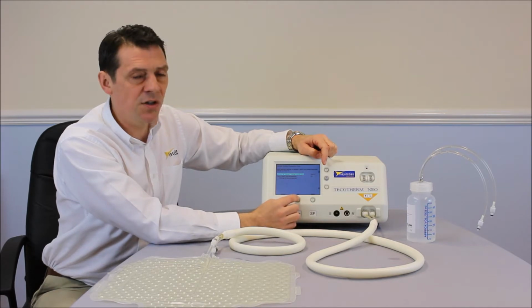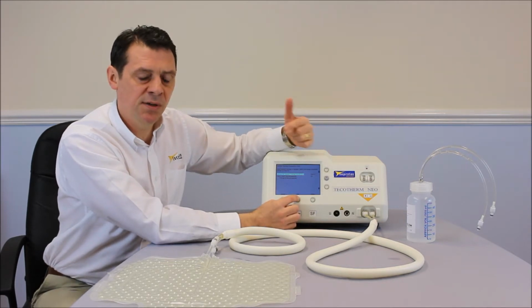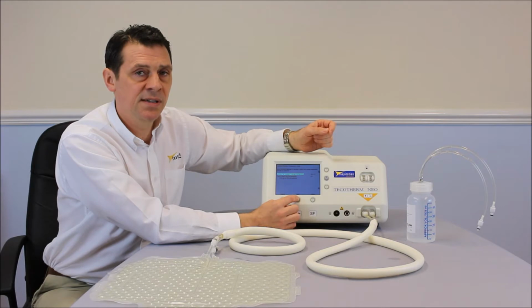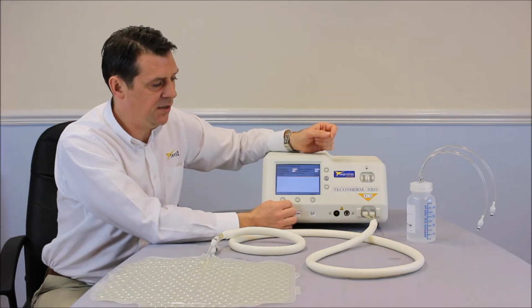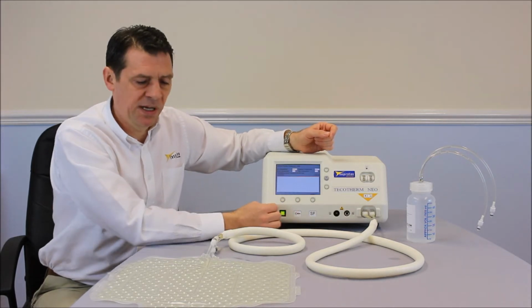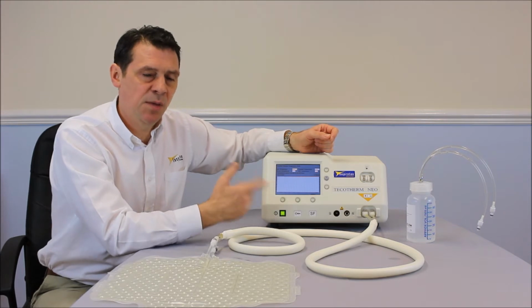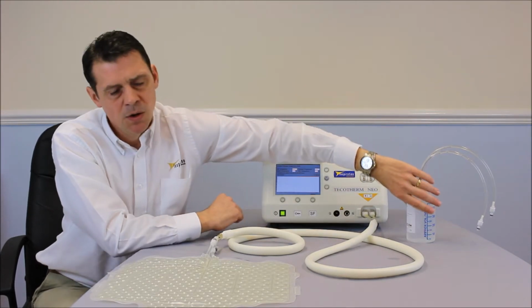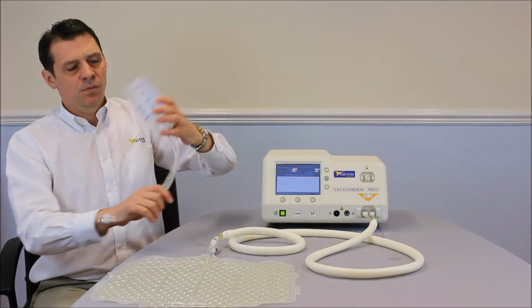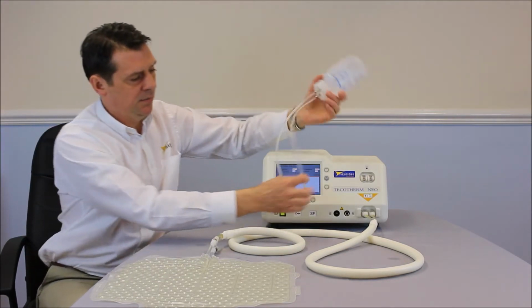If we press start, it will allow the pumps to start working to allow us to introduce more fluid into the system. Press start, and we can hear a change in tone in the machine, and the pumps are now working. To fill the mattress, we need to add the fluid via the filling bottle, and the filling ports are up here.